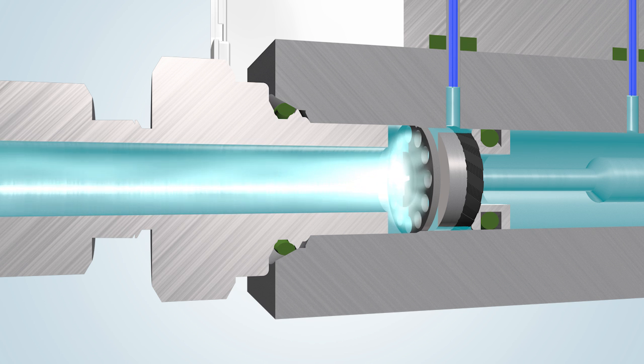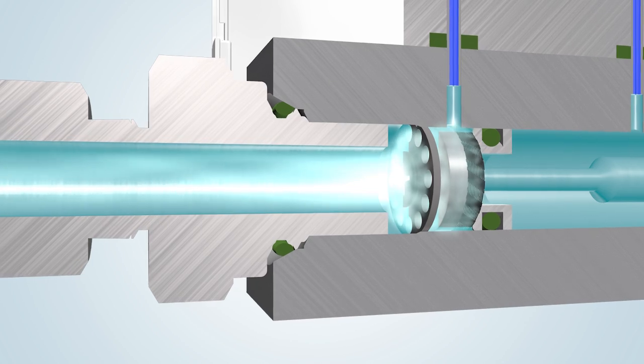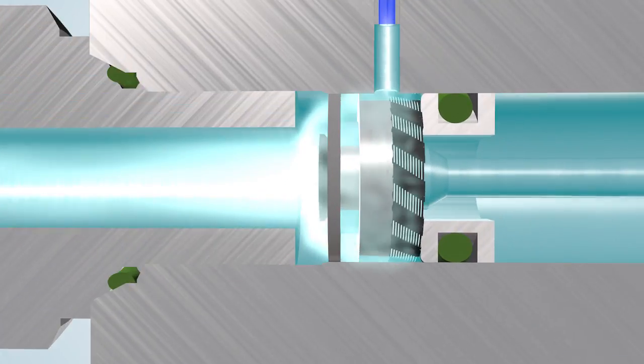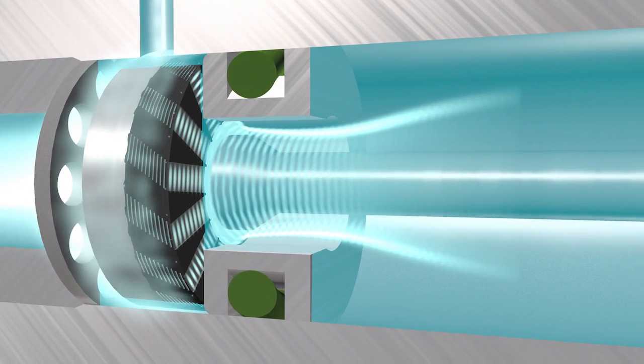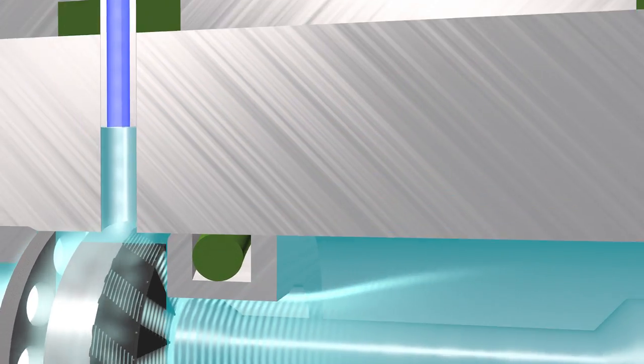The gas flows through the laminar flow element, which serves as a perfectly predictable flow resistance. This makes it possible to build and to calibrate an instrument for use on nitrogen and to model it for any other gas.